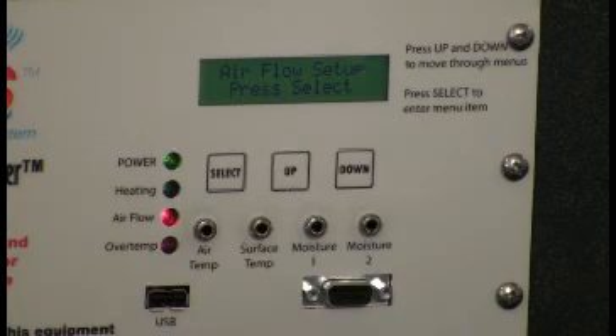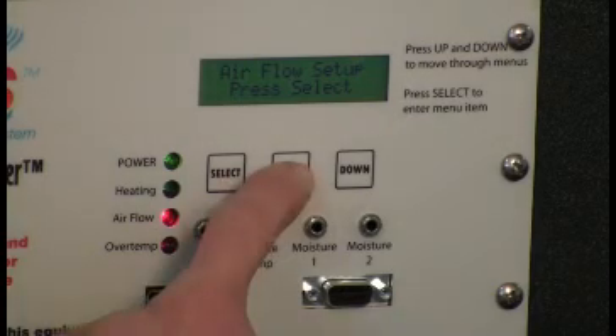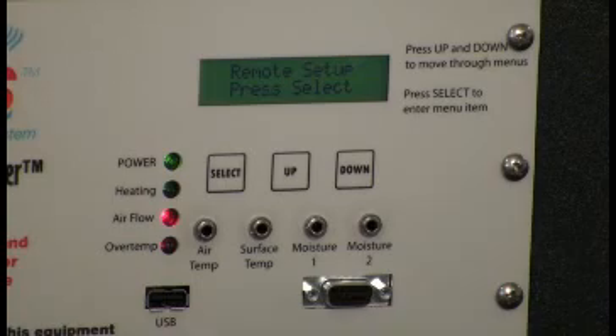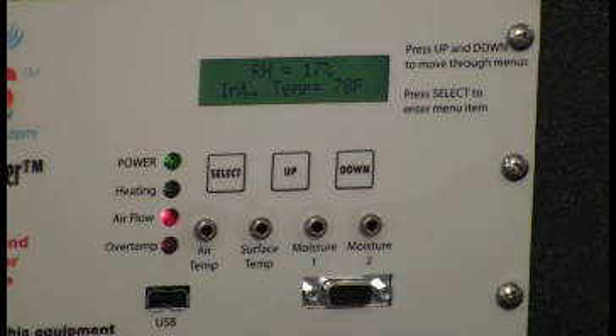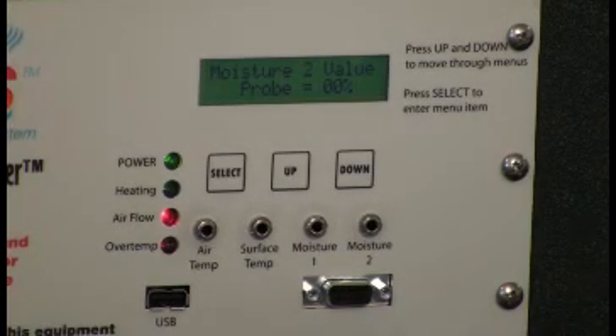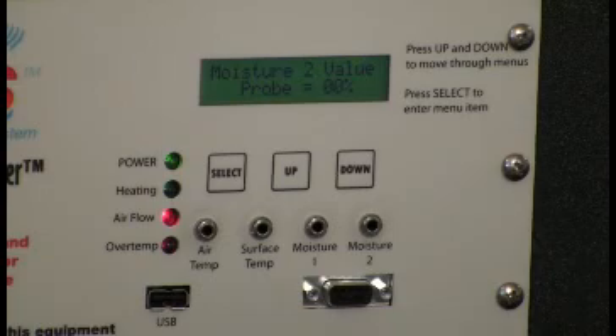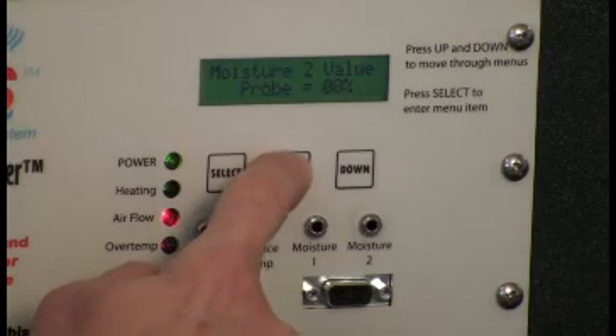The next screen is the airflow setup screen. This allows you to calibrate your airflow switch so the machine will turn on and off properly with the proper airflow. The next screen is the remote setup screen. This allows you to adjust the temperature at which your remote fan control will turn on and off. This is your internal temperature and relative humidity screen. This is your moisture 2 value screen. You can press select to enter and calibrate your remote moisture probe for number 2.